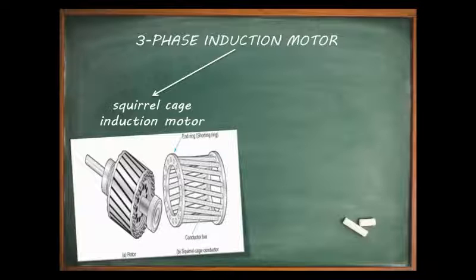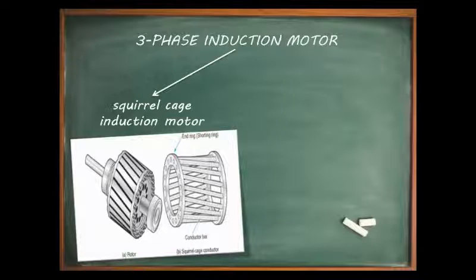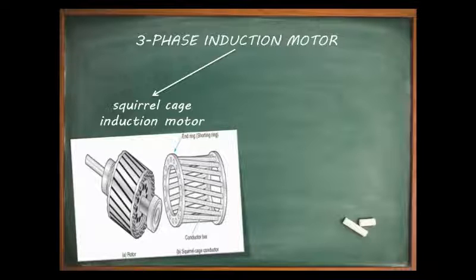At both ends of the rotor, the rotor conductors are short-circuited by continuous end rings of similar material as that of the conductors. The rotor conductors and end rings form a complete circuit that resembles a squirrel cage, hence the name. Since the rotor winding is permanently short-circuited in cage construction, there is no possibility of adding any external resistance in the rotor circuit.